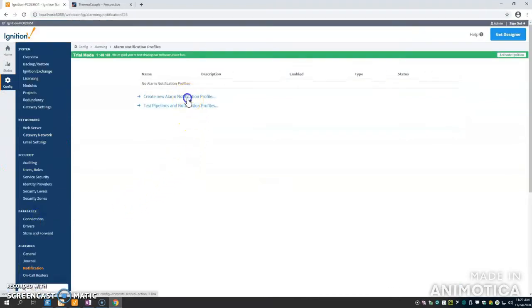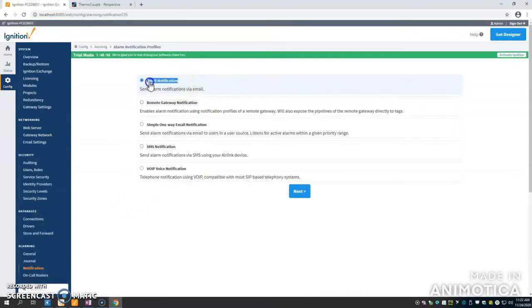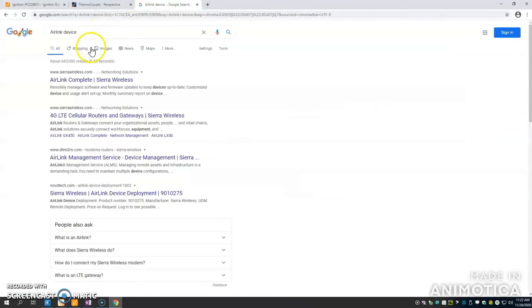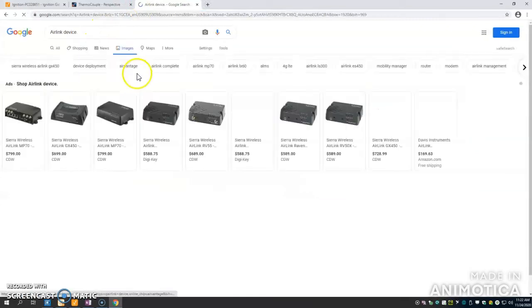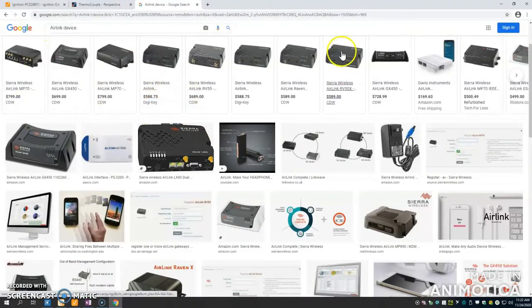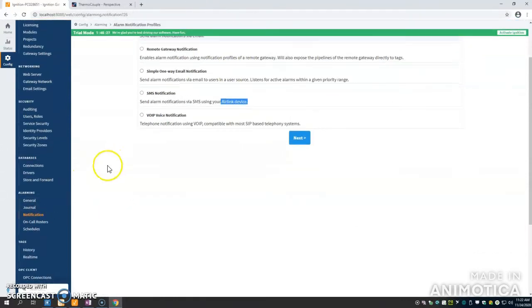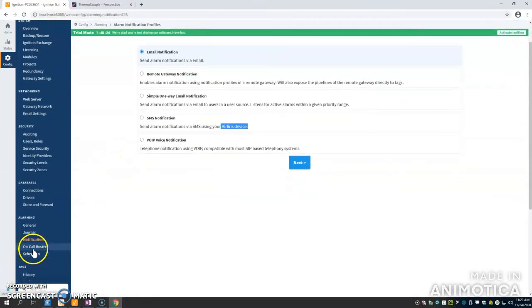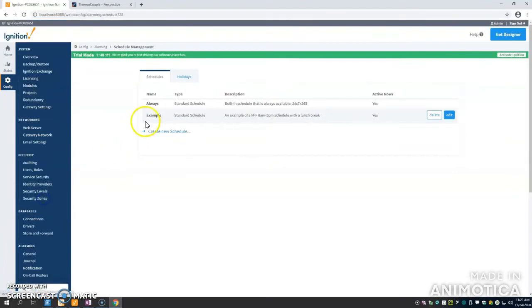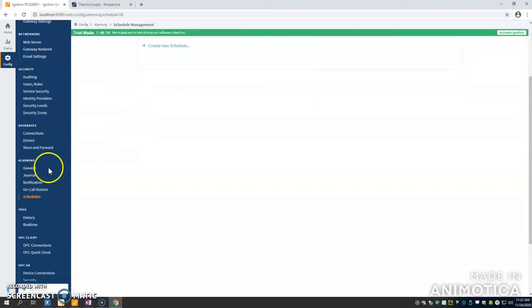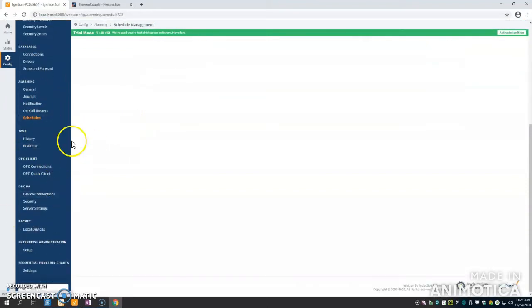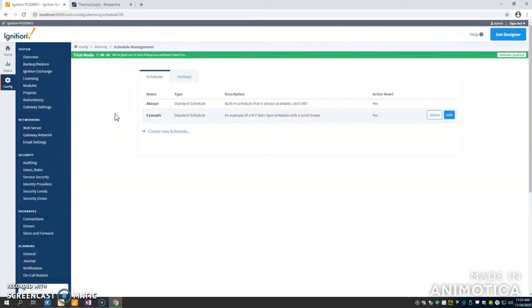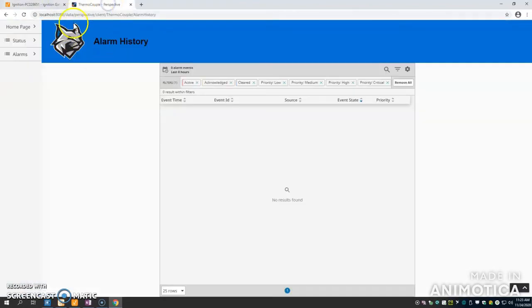But looking at the alarm notifications, you have email, SMS, email would be SMTP if you want to do calls, if you want to do an actual phone call, if you want to do SMS. If you're doing SMS, you require an AirLink device, which isn't all that expensive overall, but it's still something to be considered. There's a lot of functions that could be helpful. It's great for keeping track of everyone in maintenance or engineering on tap, up to date with what is happening. You can add schedules, even, for who's on shift. So if it's only supposed to be for people on shift, that can make it a lot more efficient as well, so you don't end up being bogged down or have people getting texts when they don't need off shift.